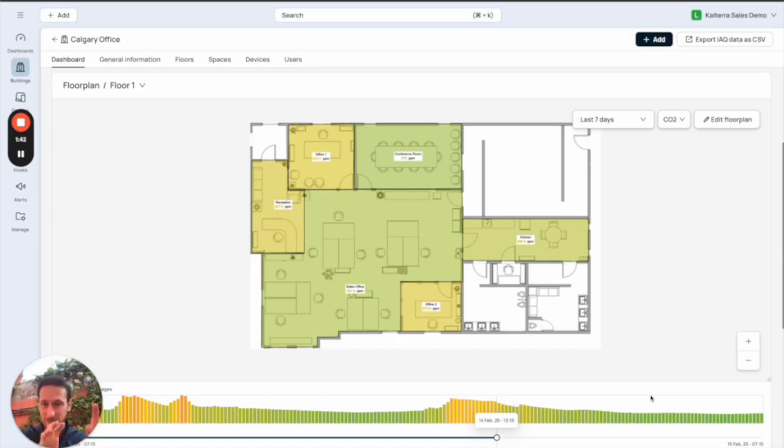And then you find all these devices, you put them on a graph, and suddenly you see all sorts of lines going up and down all over the place. It can be really, really hard to separate the signal from the noise and to extract true meaning and insight from that data. But as you can see here, just navigating through this, I'm looking at CO2 levels over time. First of all, I can see that the space performs as I would expect. There's 9-10 a.m., there's an increase, then sort of around noon it decreases, there's another spike in the afternoon over here. So that all makes sense.